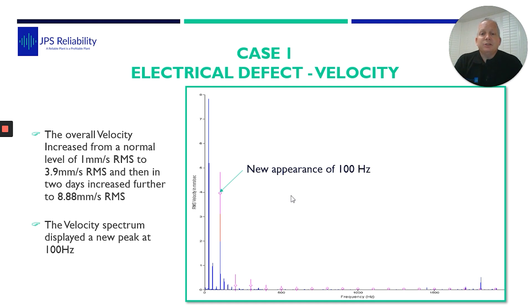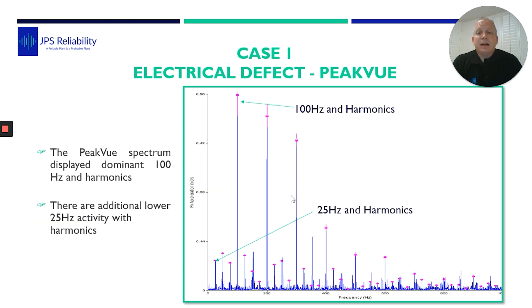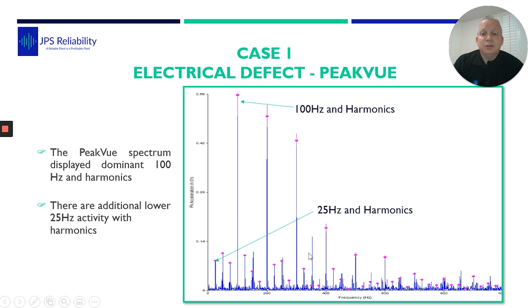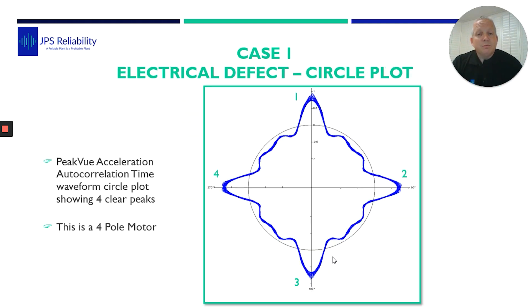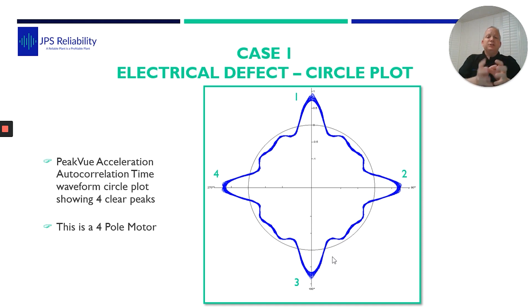So this is the velocity spectrum where we can see — which wasn't there before — a 100 hertz speed component. Then what we did, we took some PeakVue data and found lots of electrical noise, which PeakVue does tend to pick up. But this was the change in the pattern: we have lots of 100 hertz series and also 25 hertz harmonics. To look at the data differently, we put it in a circular plot. We ensured the RPM was spot on, 100%. On the circular plot you could see there are four pulses per rotation of the shaft.